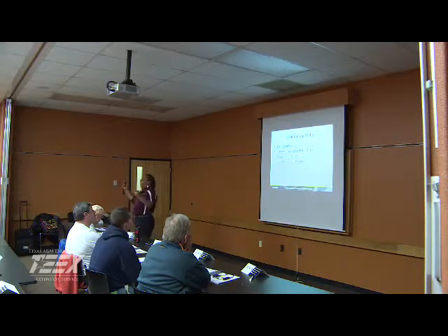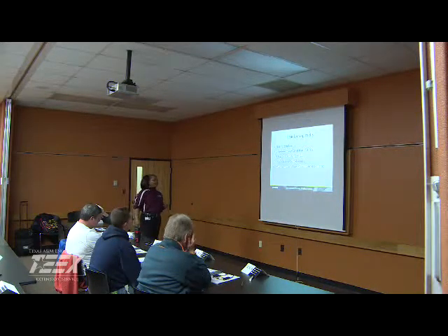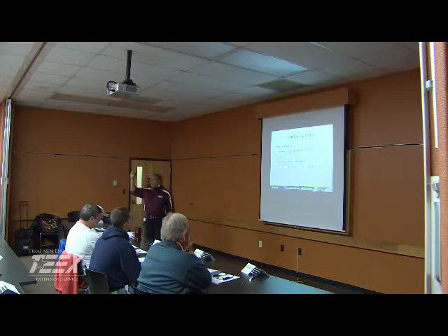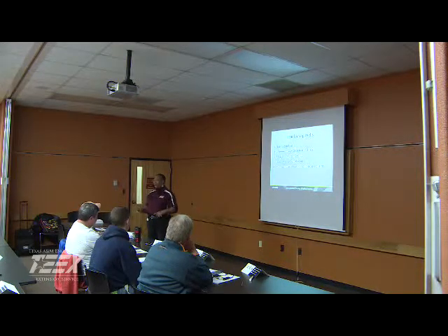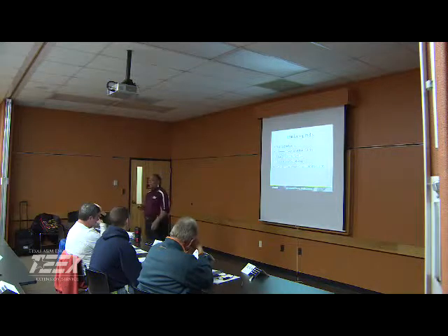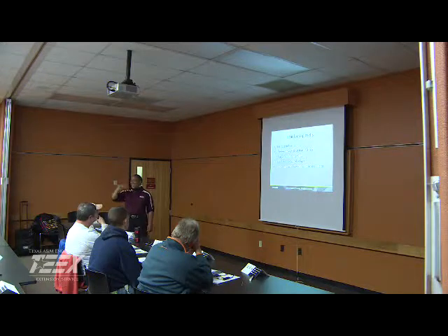Now, what will the bacteriological samples show me? Total coliform. Cool, very good. Three samples must come back negative. What happens if I come back with a positive? Yeah, you've got to go back through the disinfection. Yes, sir, that should include flushing the highly chlorinated water. Yes, you want to make sure that you do that, because that's one sure way I know I come back with a zero on my coliform. Excellent point there.